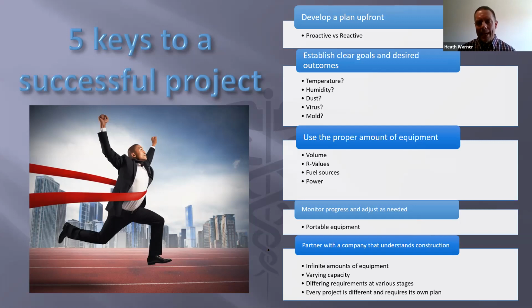It's portable. You can adapt as you need, which is point number four. Monitor the progress, adjust as needed. Use the proper amount of equipment. I can't tell you how many times I've been called in by somebody that's very frustrated because they can't control their humidity. And what they had done was somebody ran down to the Home Depot, bought two residential units, and somehow magically thought that that was going to control the humidity in a 25 or 30,000 square foot medical facility. There's a lot that goes into planning. So volume calculations, your R values, fuel sources available, the power sources that are available. Every project's different. Every project needs a custom job, custom plan, which is the very last point.